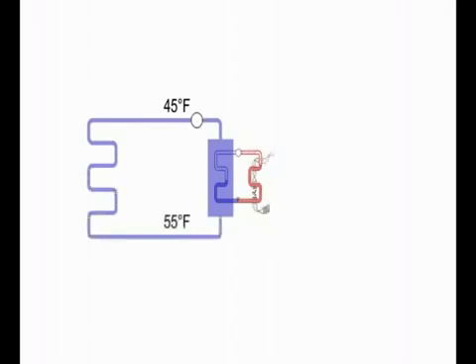Air performs reasonably at carrying cold air, but water is better at heat exchange and does a superior job keeping cold over long distances. For this reason, many buildings, and some campuses or city districts, utilize chilled water. In this regime, pumps carry water chilled on the evaporator side, which is to say the cold side, of the compression refrigeration loop, to sometimes distant air handling units.